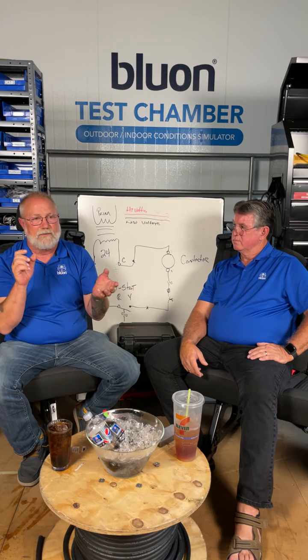But it's not just as easy as taking the thermostat wire and connecting it to the contactor, not on a defrost board, because you've got to jump out, make sure that the outdoor fan motor runs, that your pressure switches are all there. Obviously, if the board's bad, the temp sensors aren't going to function, and that's not going to do anything in your bypass moves. But you may have to hook up relays. You can do it, but just be aware and ask yourself, what is this board doing? And if I bypass this, what are the consequences that can occur?